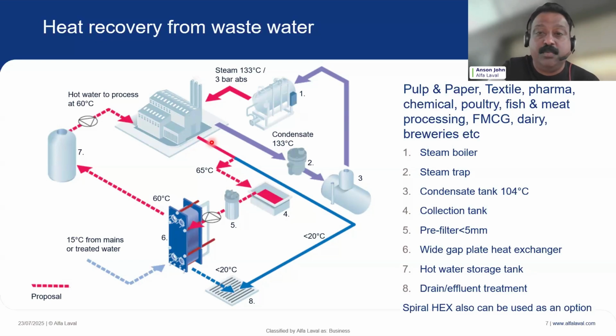But to counter that, we are using what we call a wide gap plate heat exchanger, which has a bigger pressing depth in the plate, like 8 mm or close to that, and that will allow a lot of particles to pass through the plate type heat exchangers, because in the plate it's not laminar flow. Most of the time it's turbulent flow, so the particles don't stay. At the same time, you can also use some filtration to take out bigger particles than that. Using spiral heat exchangers also makes a lot of sense if you've got bigger particle sizes. And these are pretty common applications which we do.